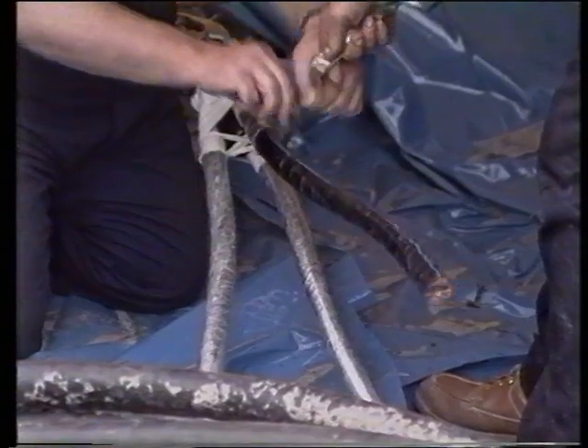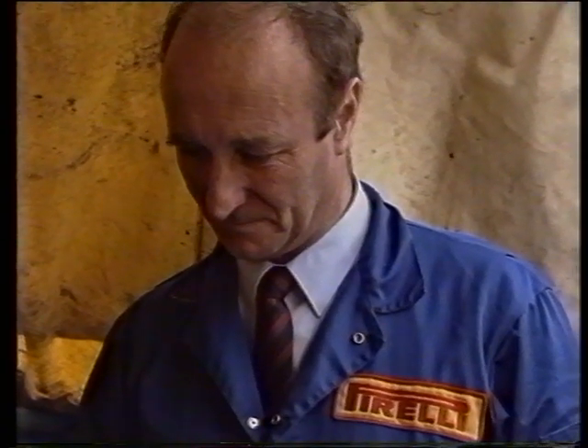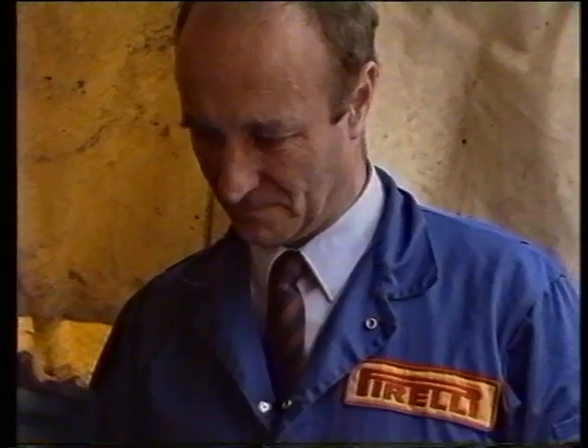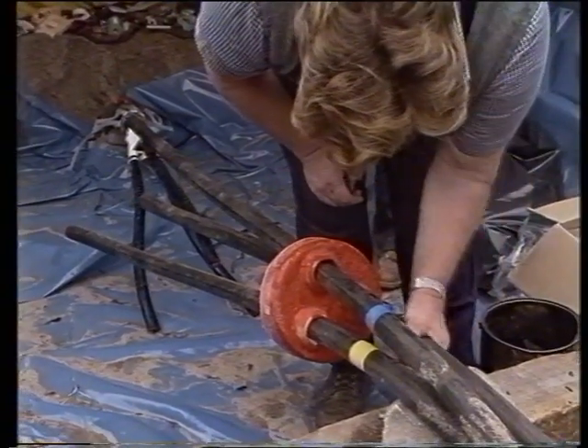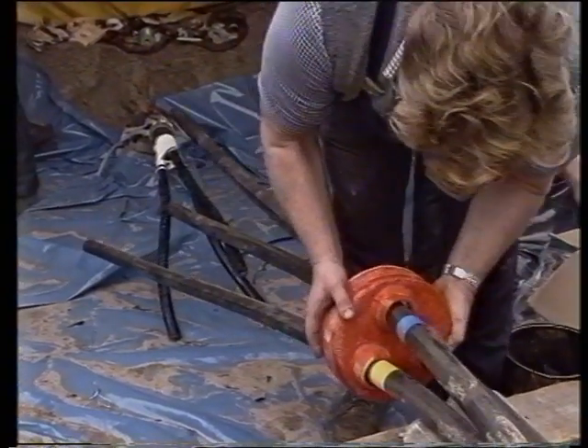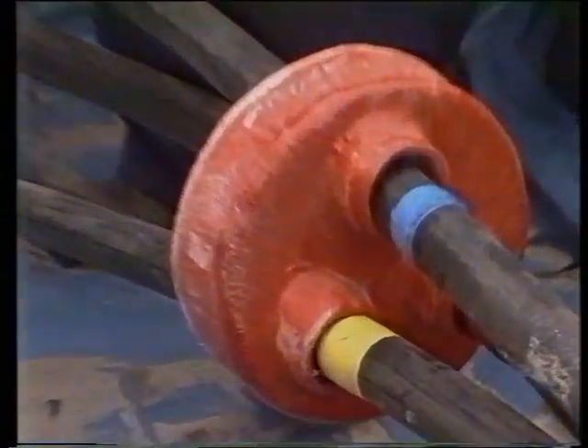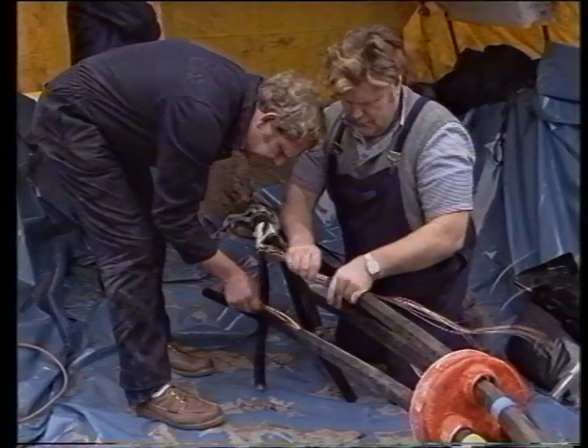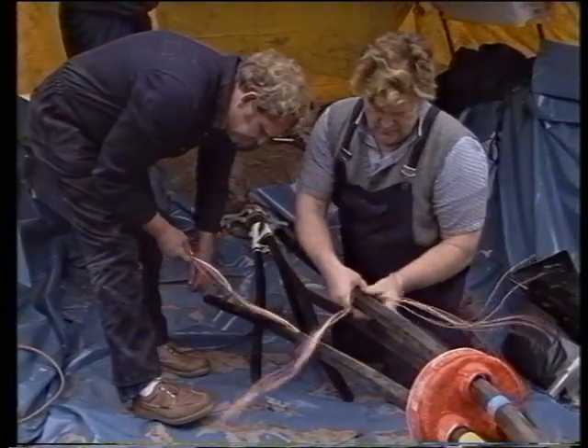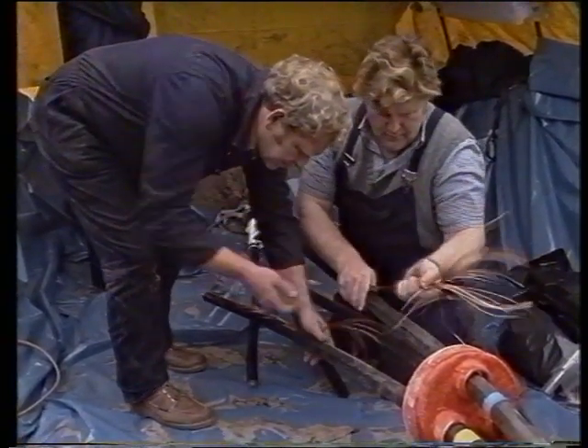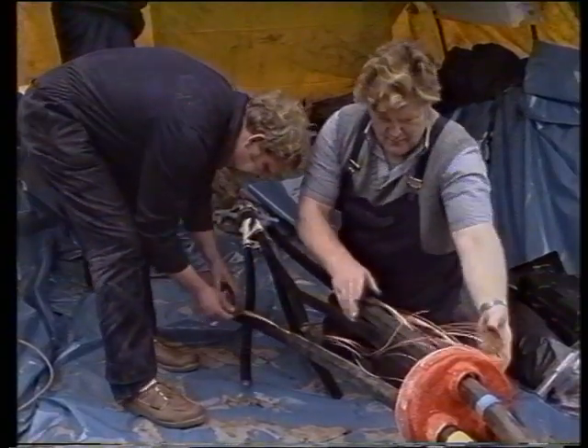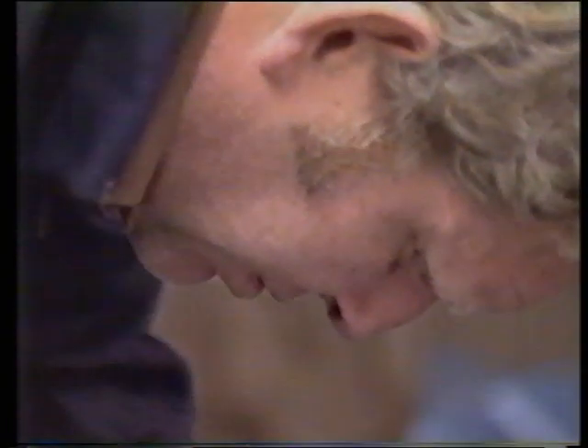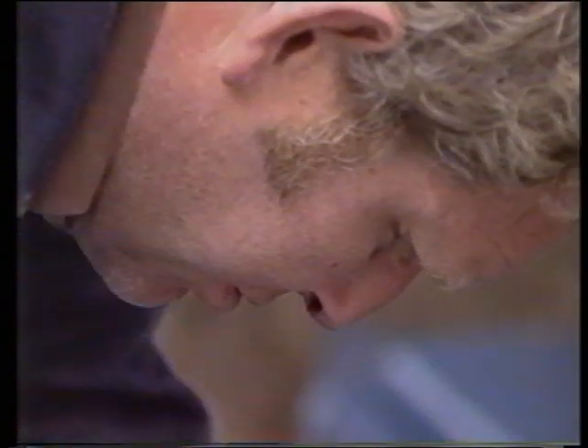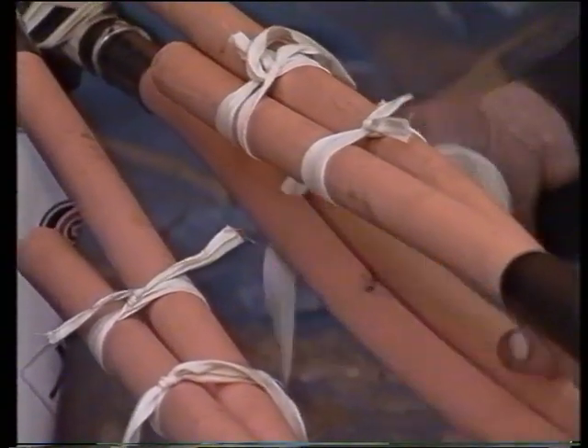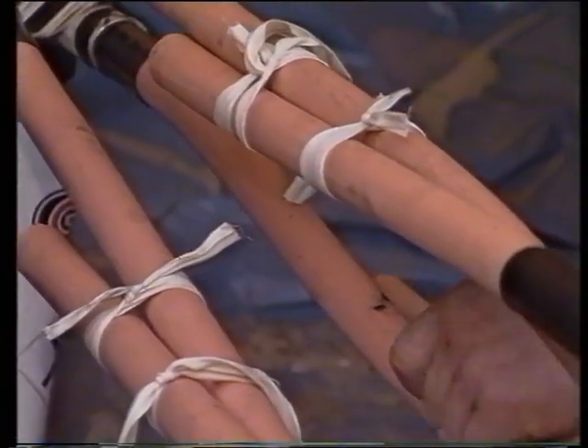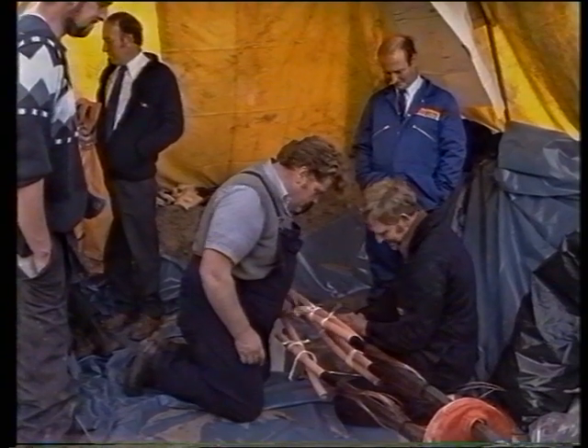A watchful eye is kept on things by a man from Pirelli. To make sure the land cables can easily be identified later, each phase is colour-coded as it's placed in a spreader for the next stage. Again, the cables are stripped back in the same way as the submarine cable has been. The 2 sets of naked cable are laid alongside one another and bound together to make sure there's plenty of spare to make the joint properly.